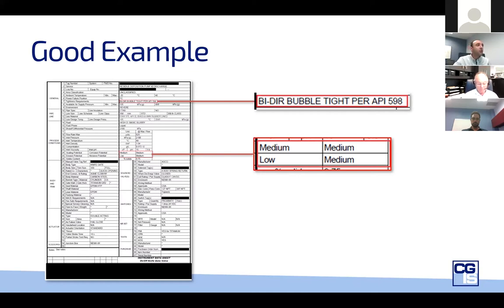I still don't have the normal operating position — is it normally open or normally closed? Especially for scaling, that's a critical piece of information for me to make good assertions on the selection of the valve and the actuation.